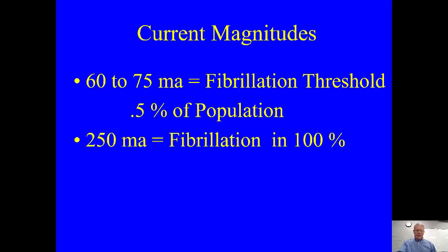At 250 milliamps, 100% of the population is going to go into fibrillation. So on a 15 amp breaker, 250 milliamps is a quarter of an amp—4 times 15 is 60. That means 60 people could go into ventricular fibrillation on this 15 amp breaker and die, and it wouldn't trip. It does not take that much to kill us. That's the point of all this.